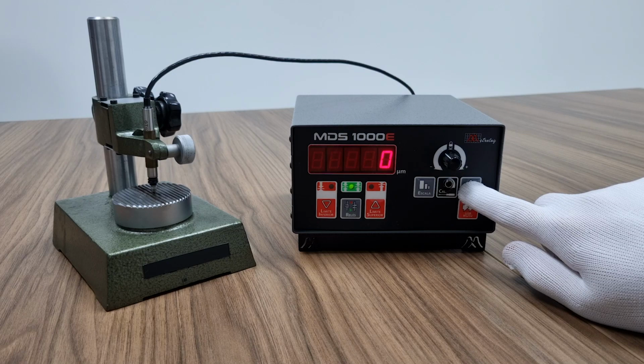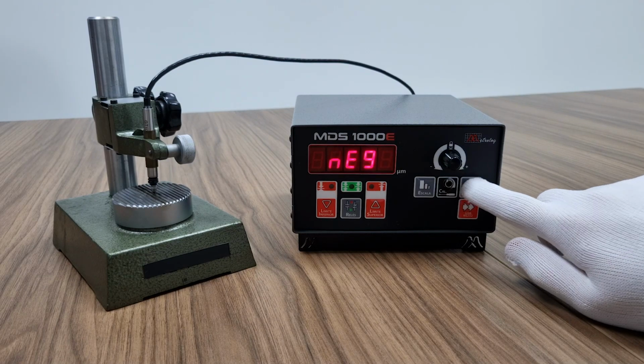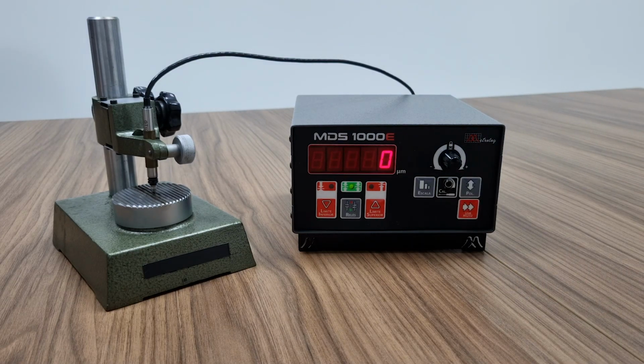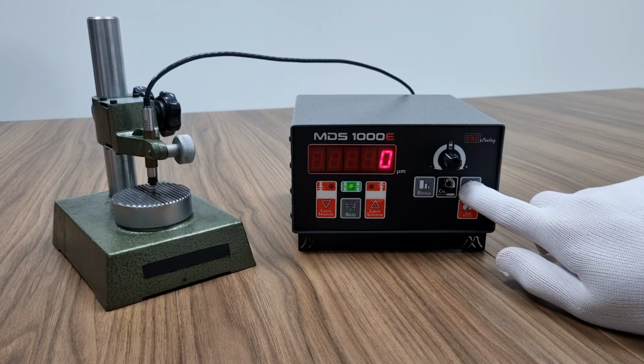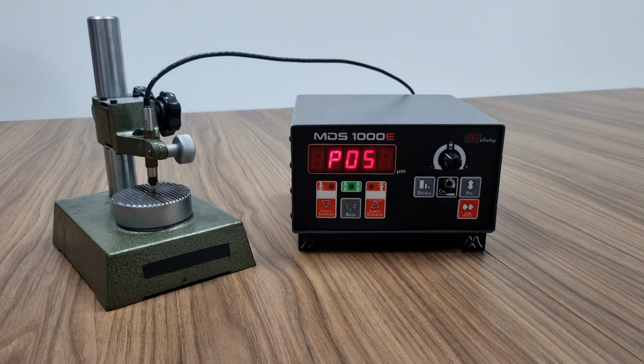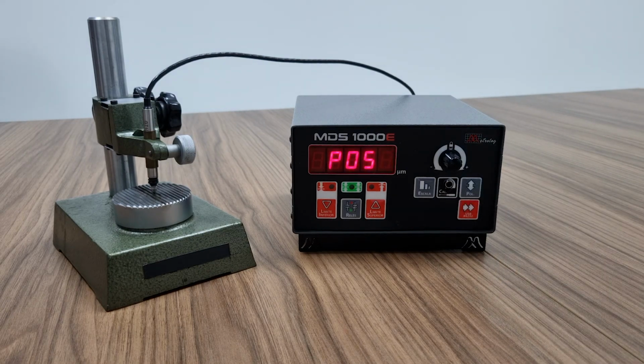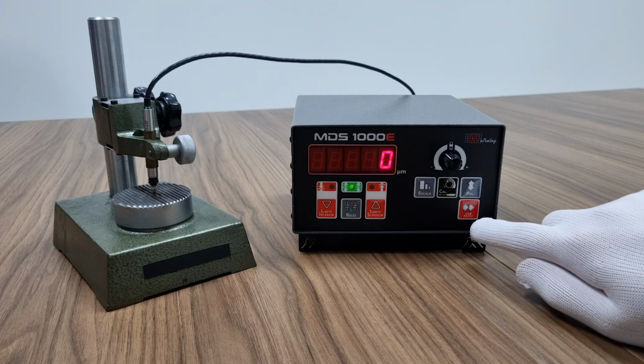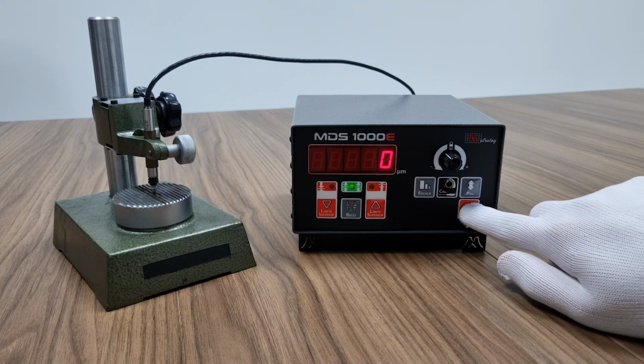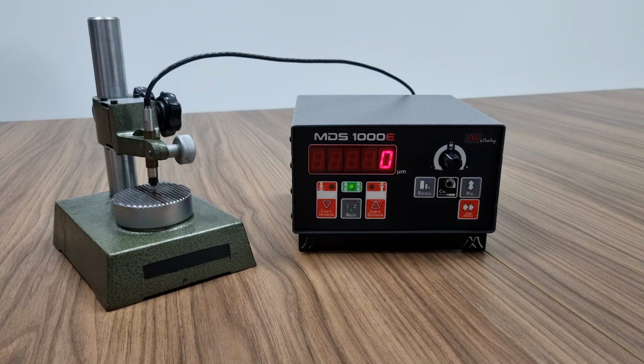The POL key allows you to adjust the direction of the sensor reading increment in either the positive or negative direction. To toggle the polarity, press the key for 2 seconds. The key can be pressed briefly to query the set value. The USB RS-232 key transmits the current reading to the communication interfaces.